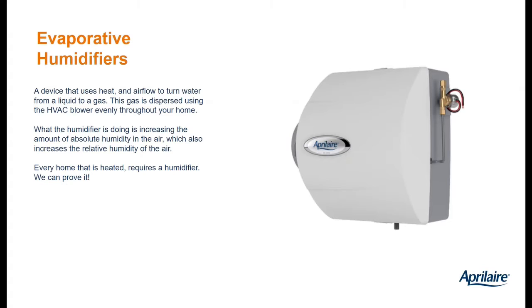We're going to be talking about our evaporative humidifiers today. The key thing about an evaporative humidifier is the humidity that's being introduced into the ductwork is a gas. The water leaves the water panel as a gas. So it's not spraying out a fog or a mist. So we don't have to worry about rusting or water damage, anything like that, because the moisture is already a gas. Water vapor is going to pass through filters and blowers and everything else, just like the oxygen in the air passes through the filter and the blower.